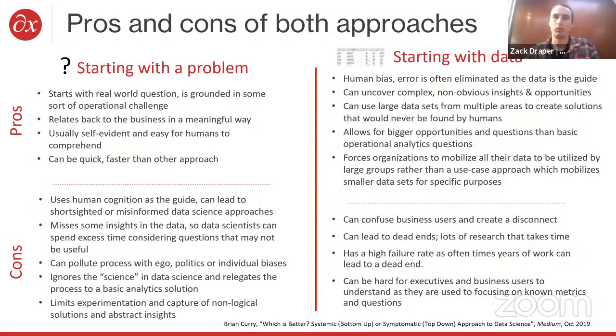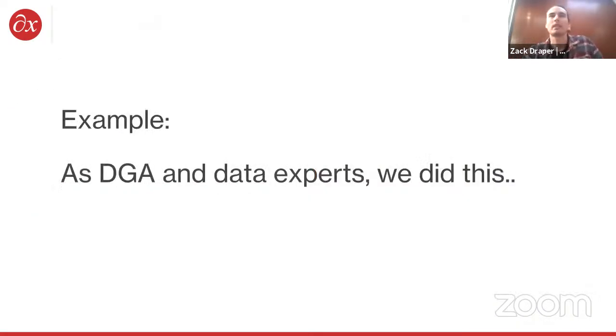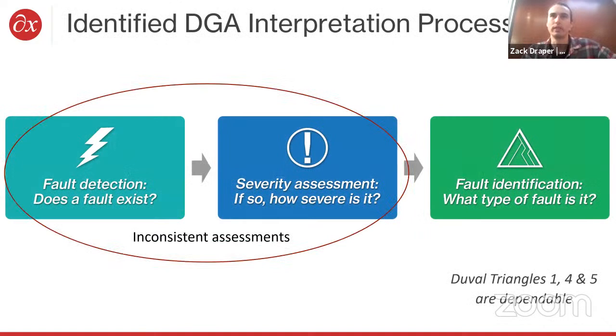And ultimately, there's no one right way in this. It's often something that has to be balanced between figuring out what the problems are that actually need to be solved and seeing what the data can actually tell you about those problems. So for an example, what we'll talk about is how DGA has been interpreted. One of the things that we found is that there are some inconsistencies in the assessment. So DGA is sort of a three-step process where you're identifying: is there a fault in the transformer or not? And if there is a fault, how severe is that problem? Figuring that out has been sort of a gap in our understanding in the DGA process.